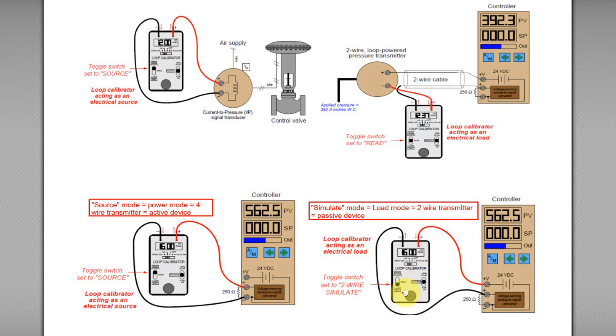The signal calibrator switch is set to simulate mode. Simulate mode is opposite to source mode — it will make the loop calibrator become an electrical load. Although it does not power up the whole circuit, it will inject the signal to the circuit. The controller terminal will act as the electrical source, because this wire is connected to positive V, which is internally connected to the controller's internal power source. So this power source will power the whole loop.